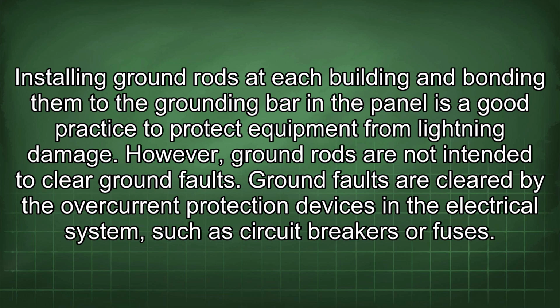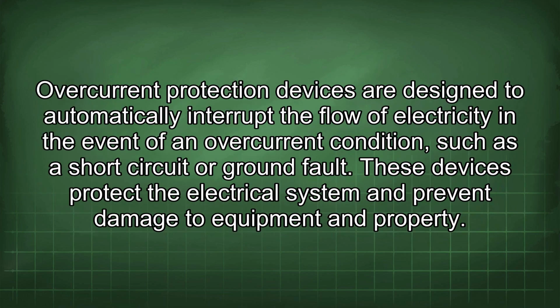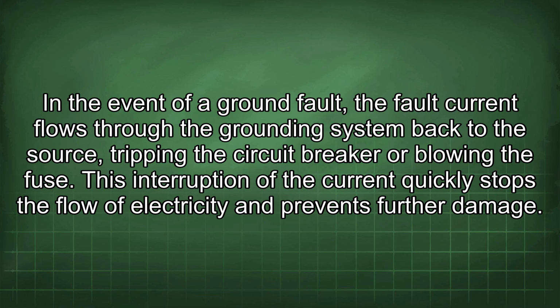Ground faults are cleared by the overcurrent protection devices in the electrical system, such as circuit breakers or fuses. Overcurrent protection devices are designed to automatically interrupt the flow of electricity in the event of an overcurrent condition such as a short circuit or ground fault. These devices protect the electrical system and prevent damage to equipment and property. In the event of a ground fault, the fault current flows through the grounding system back to the source, tripping the circuit breaker or blowing the fuse. This interruption of the current quickly stops the flow of electricity and prevents further damage.